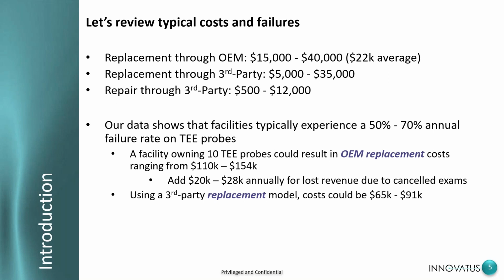So our data shows that facilities typically experience a 50 to 70% annual failure rate on TEE probes. So when Ted Lucidi or myself do an analysis at a hospital, and they tell us they have 20 TEE probes, we make an assumption that about half of those probes will have some type of failure over the course of a year. So if we extrapolate the numbers from our facility that owns 10, replacement costs can be anywhere between $110,000 and $154,000.